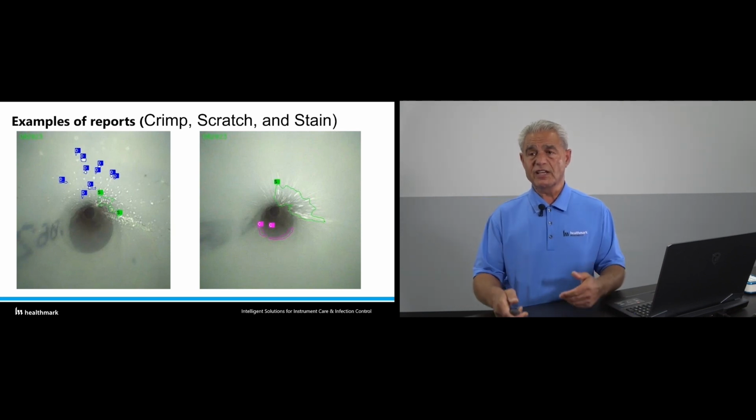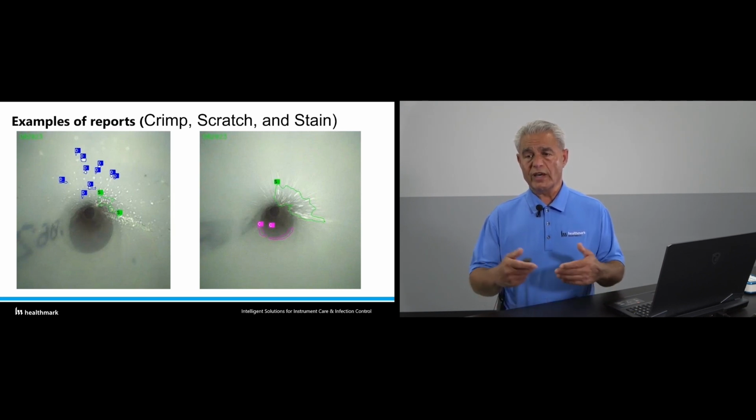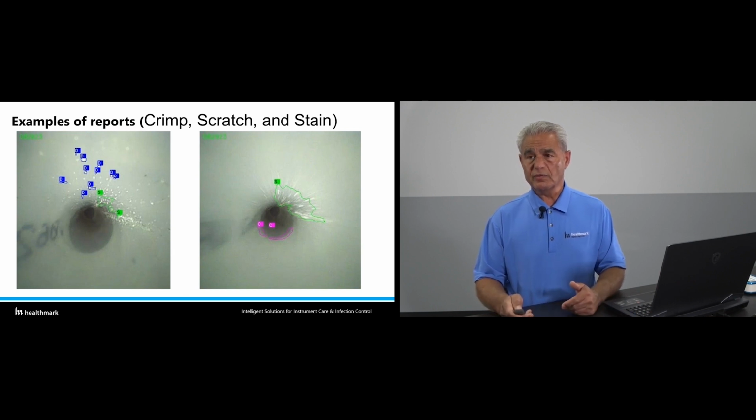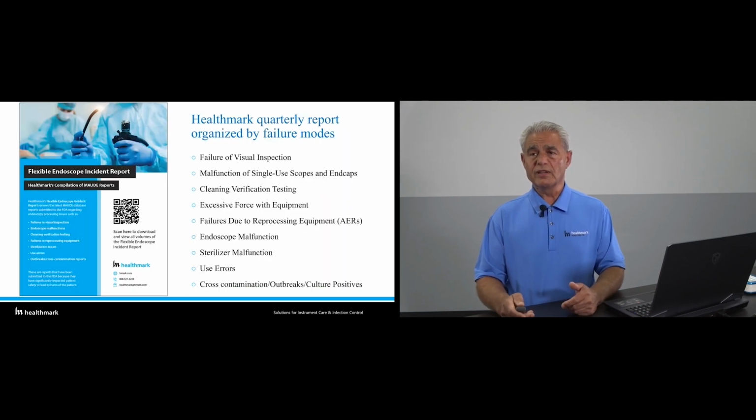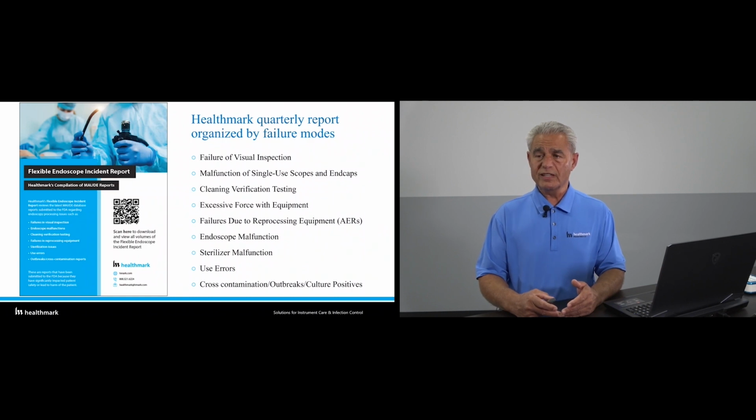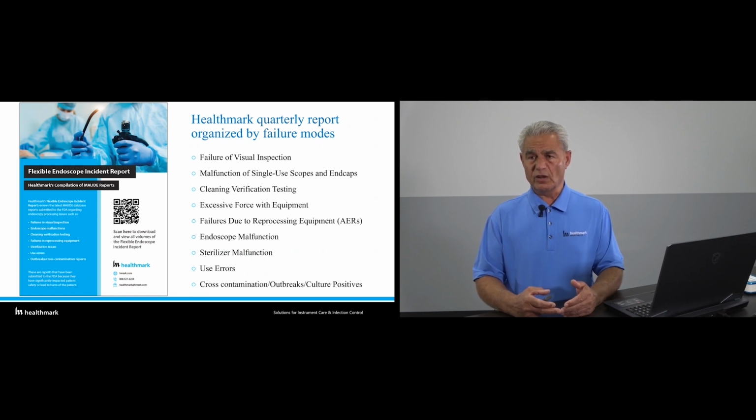It learns constantly. As you move forward, you can teach it the issues with abnormality, or if you have an issue internal. So as we get more and more pictures, those buckets of various items are going to get more enhanced and more information is going to come out of that. Part of this, obviously, the inspection with borescope and this artificial intelligence, is really to reduce all the issues that have been reported to the FDA MAUDE database.